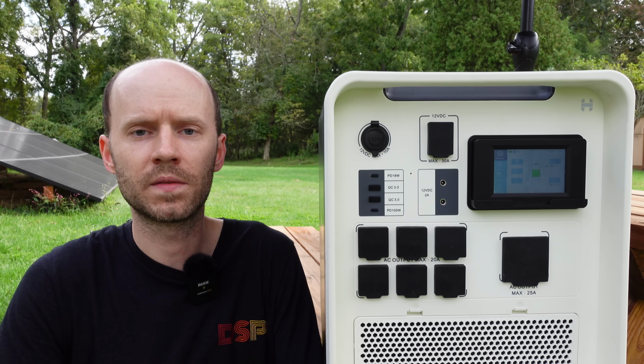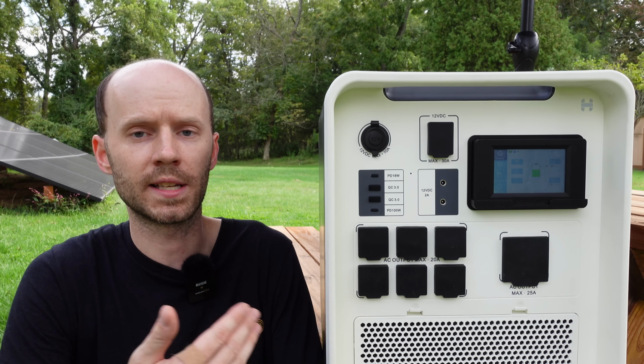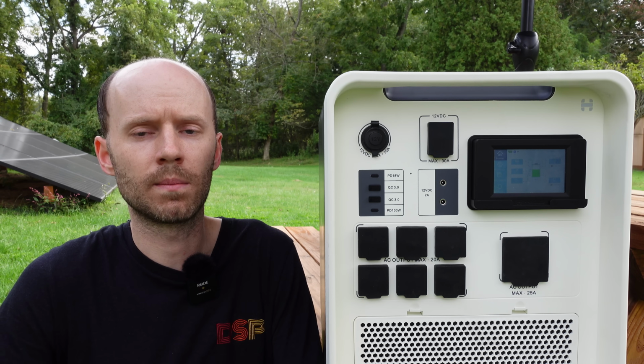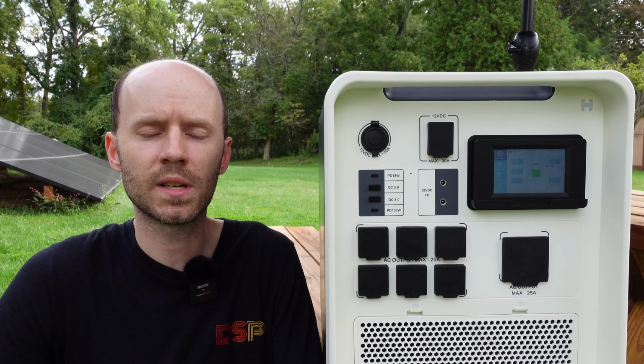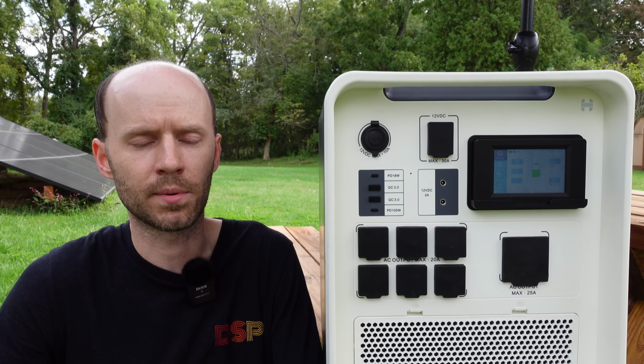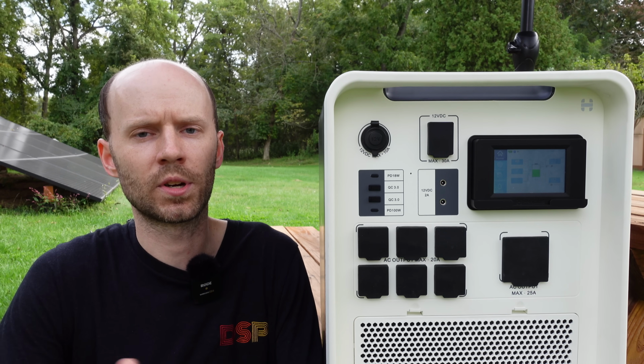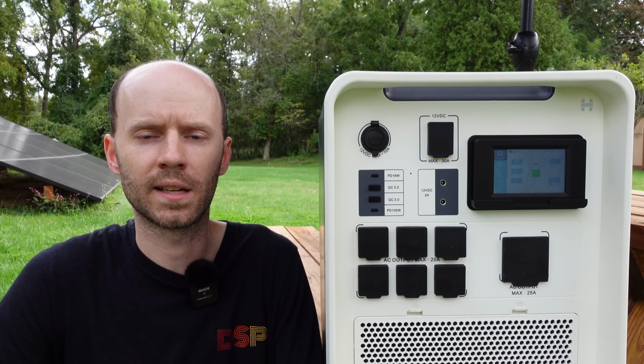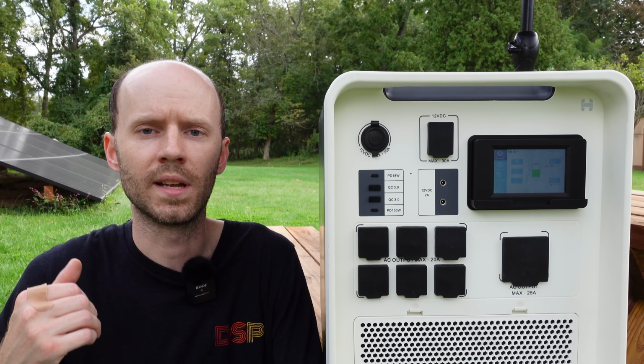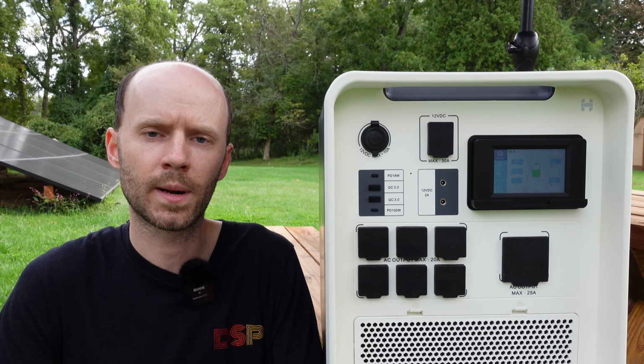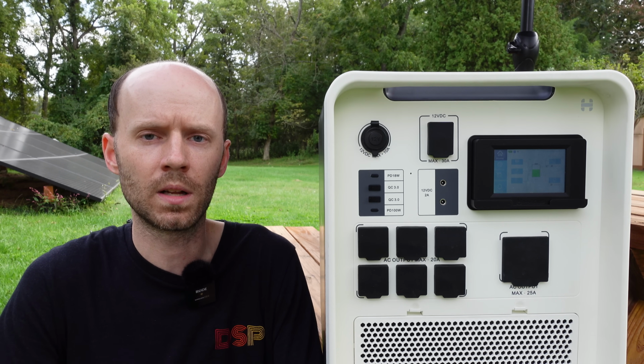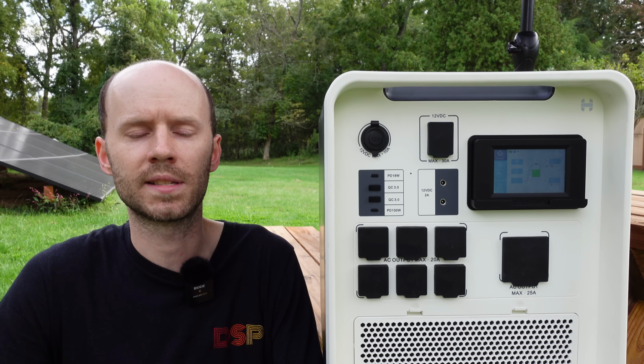If you need more power, it's very easy to stack 2 or more of these in a split phase configuration, or a multiple 120 volt configuration to increase the output capacity, the output amperage. And if you're going to start stacking 3 or more of these, I'd say you'd probably want to consider getting an electrician out just to make sure you're using the right gauge conductors, the right circuit breakers for overcurrent protection, the right breaker panel, all of the right wiring components to remain safe in your setup.